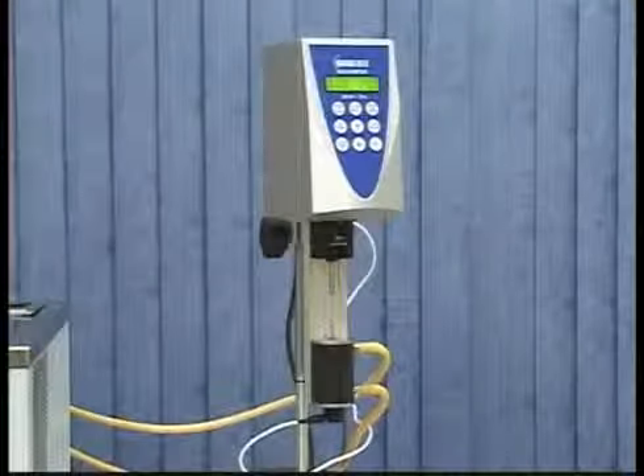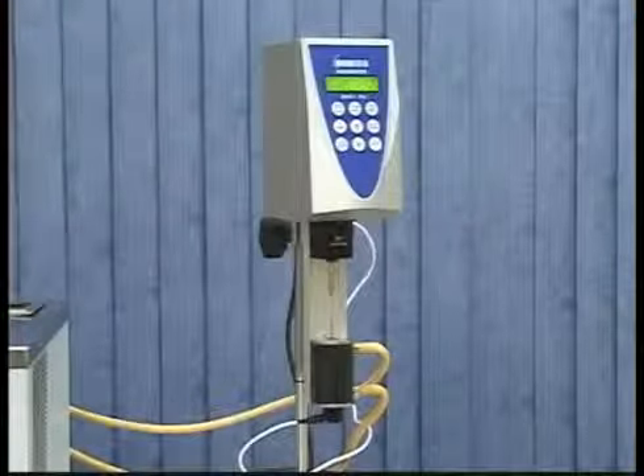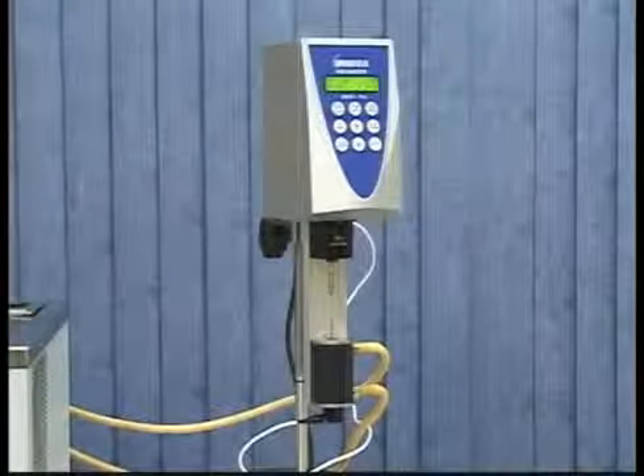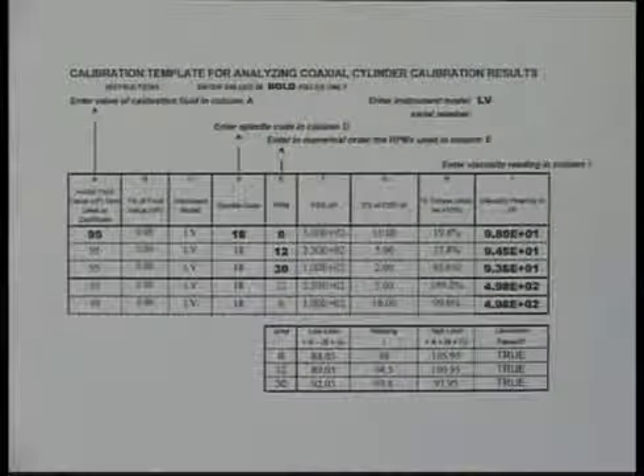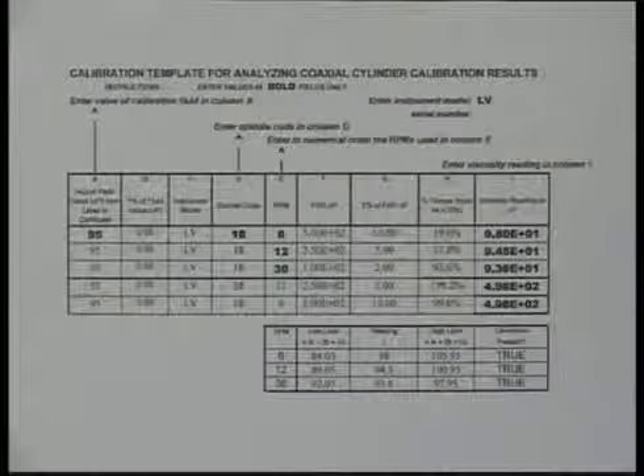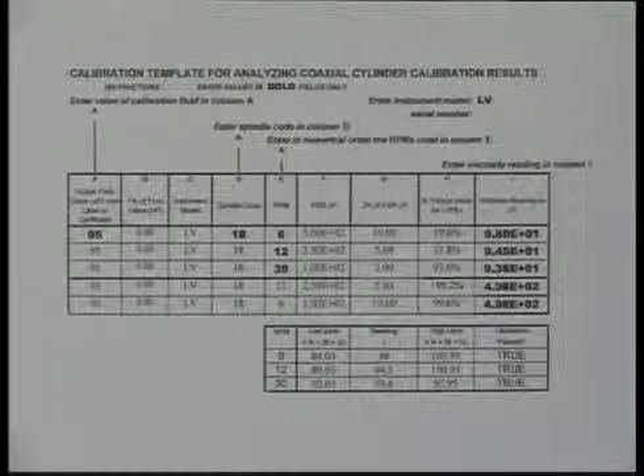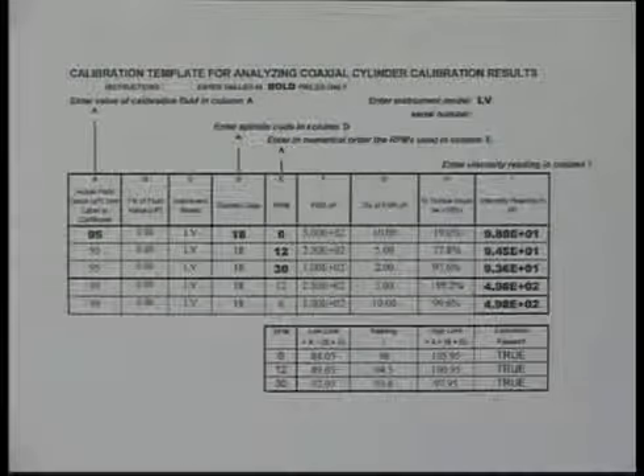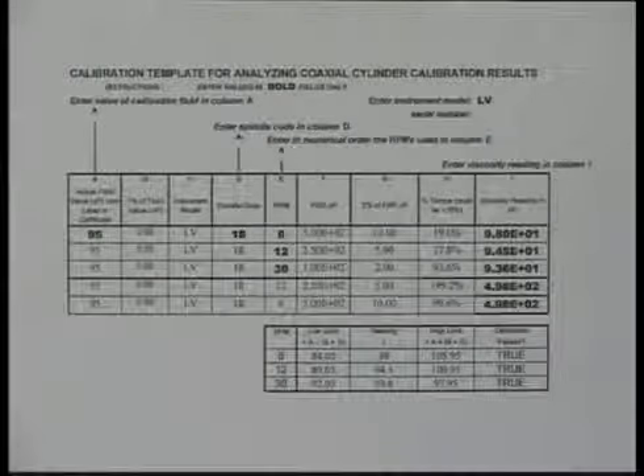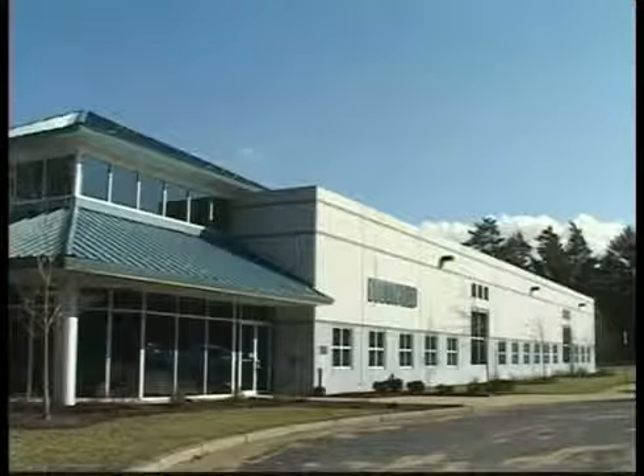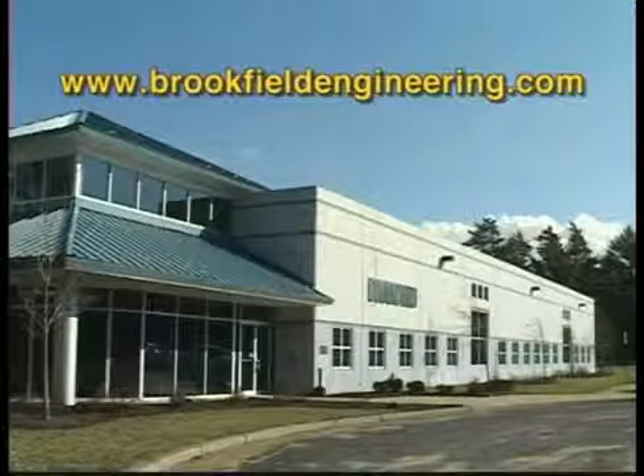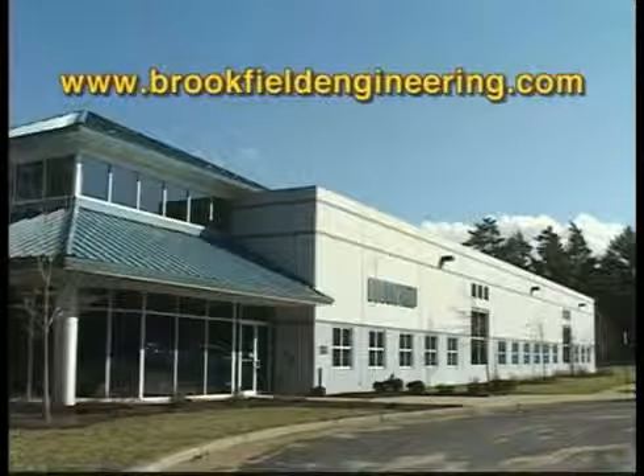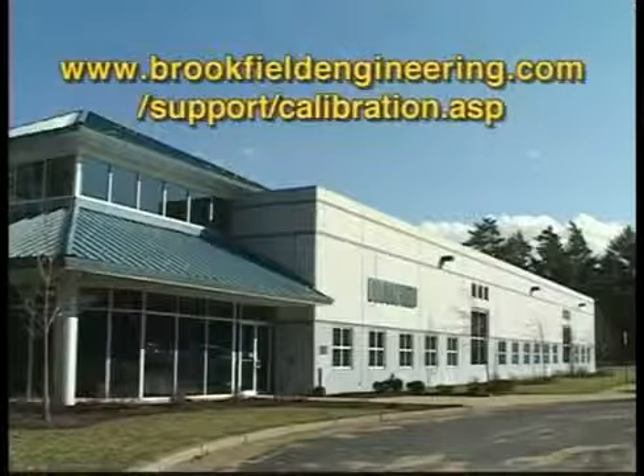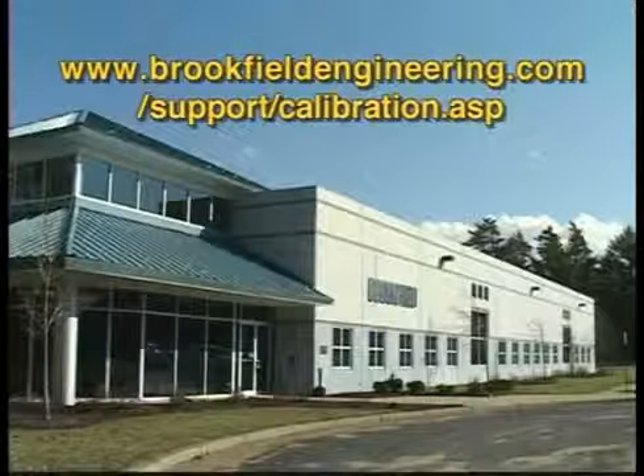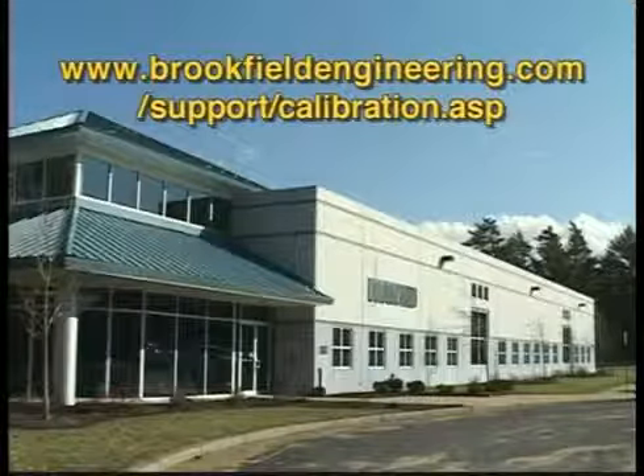You can perform a calibration check manually and enter the values and compute the tolerances for pass-fail criteria. Brookfield also supplies a calibration worksheet on our website that easily allows you to enter data, computes the tolerances for each range, and gives pass-fail criteria automatically. You can download the calibration worksheet from Brookfield's website at www.brookfieldengineering.com. Going to the link on your screen will take you directly to the calibration worksheet.